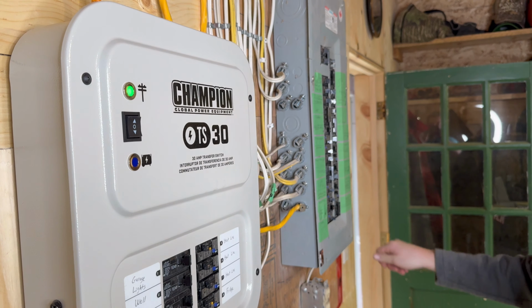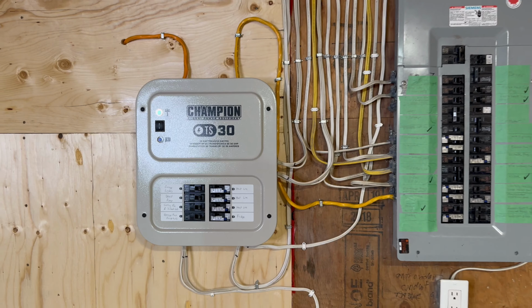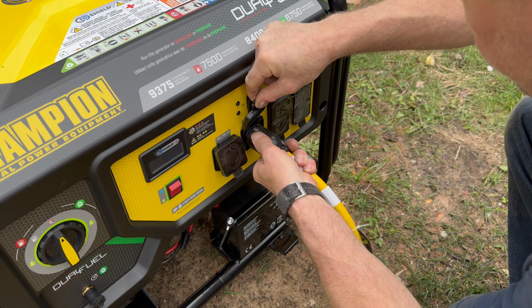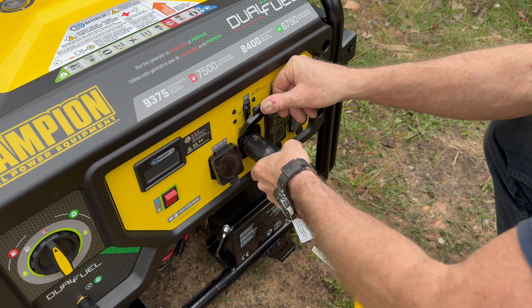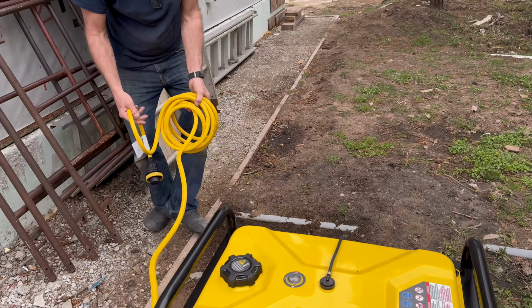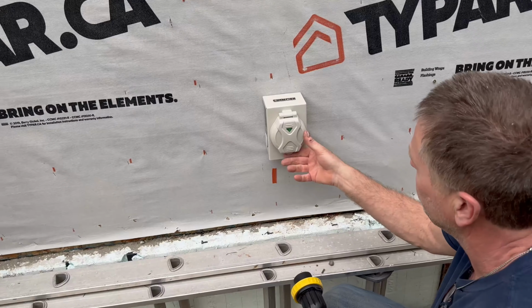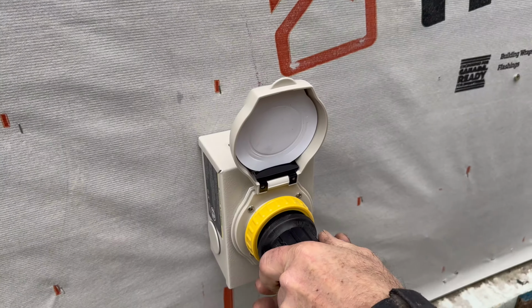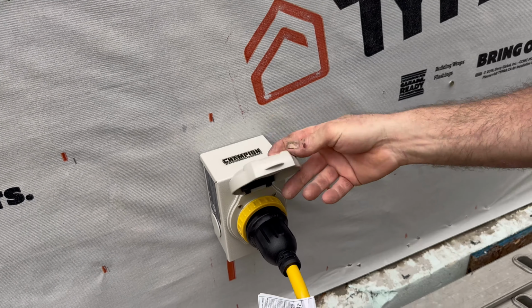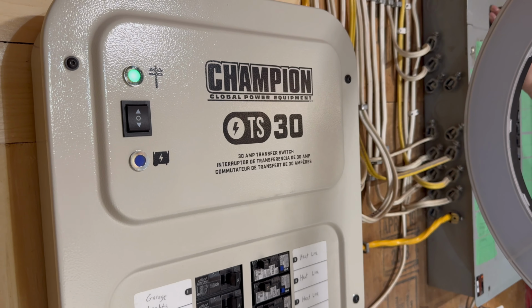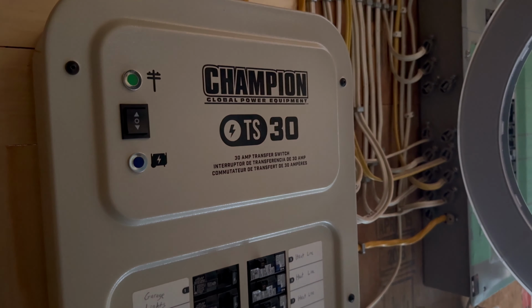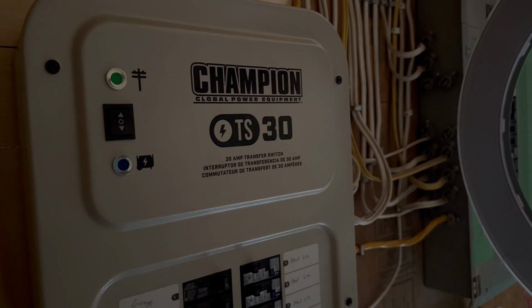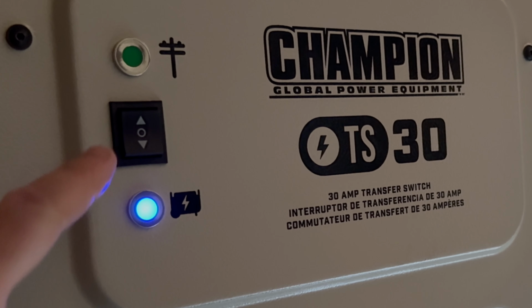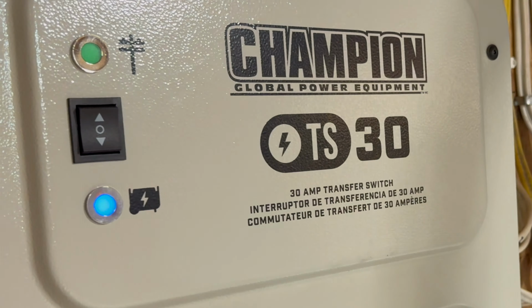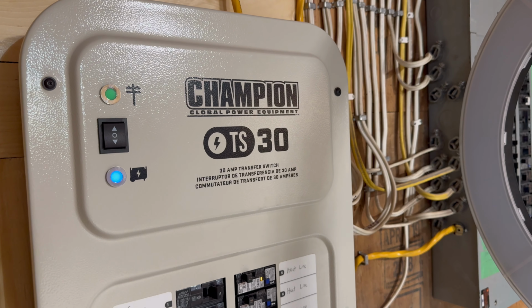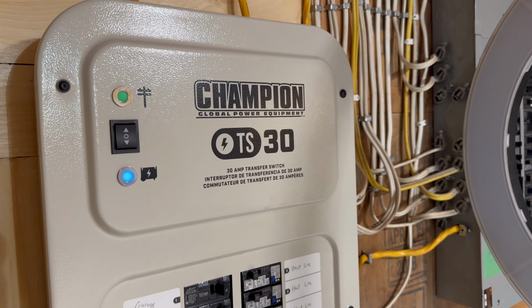No transfer switch installation would be complete without testing. So begin by firing up the generator, then make the connection with the cable to the generator itself, and then the inlet port. And when these things are connected, run a test, switch the main breaker off on your panel, and then hit the generator activation button to make sure the generator power really does power all of the circuits that you had in mind.